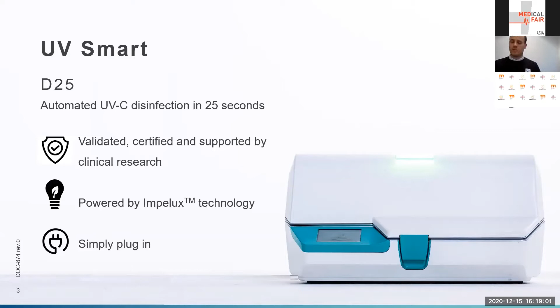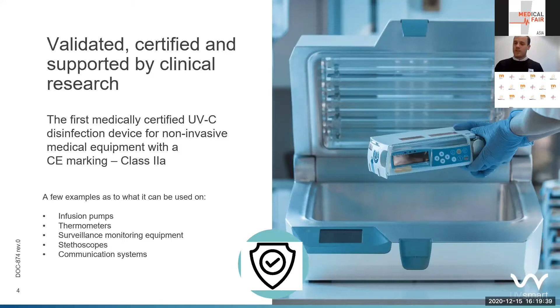As I mentioned earlier, the device is validated, certified, and supported by clinical research. We are the first medically certified UVC disinfection device for non-invasive medical equipment. We have a CE marking of class 2A, so we're an active medical device. We're also fully ISO 13485 certified, and it's all done under the MDD. A few examples: thermometers, surveillance monitoring equipment, stethoscopes, communication systems, actually everything that goes from patient to patient. Everything that goes on the skin of the patient or around the patient can be disinfected in just 25 seconds.